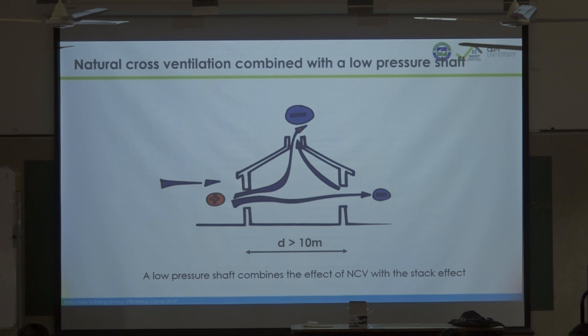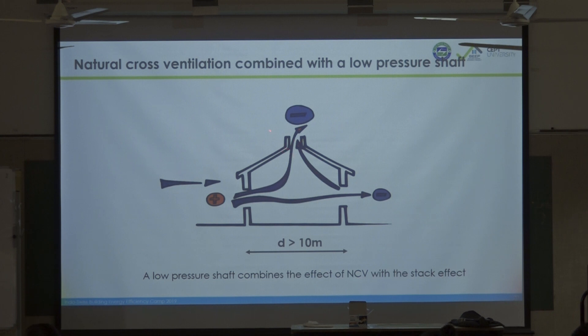If the thickness of the building exceeds 10 meters, natural cross ventilation is not enough because of air friction. An interesting solution is what I call a low pressure shaft: you create an opening at the top of the roof that generates a Venturi effect — the wind is captured and accelerated by these shafts, creating a low pressure at the top of the roof.